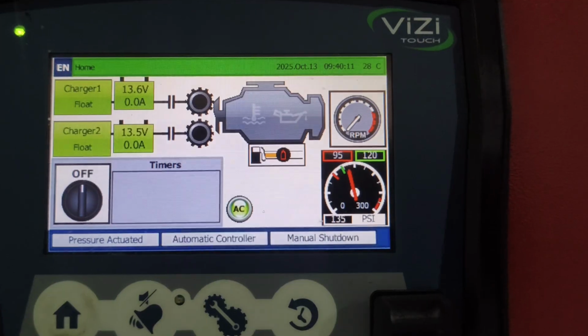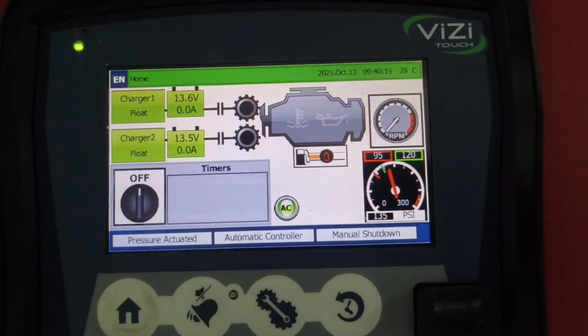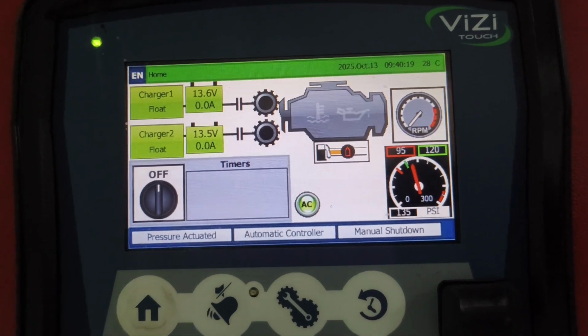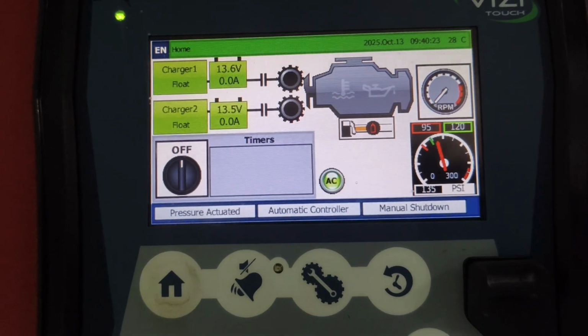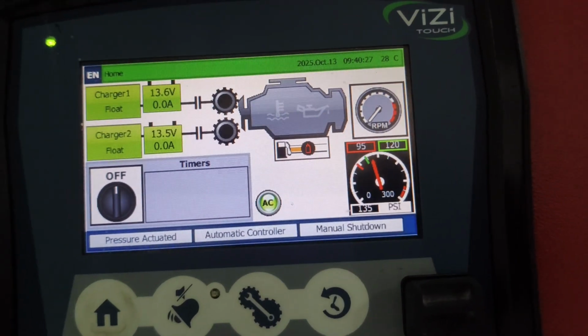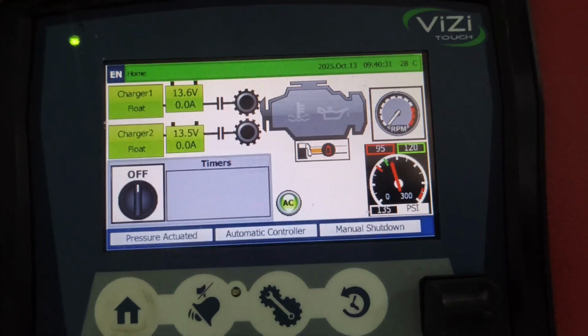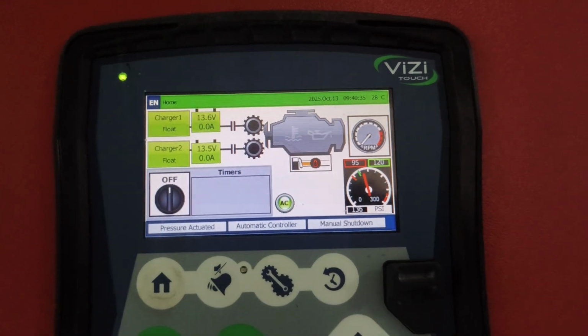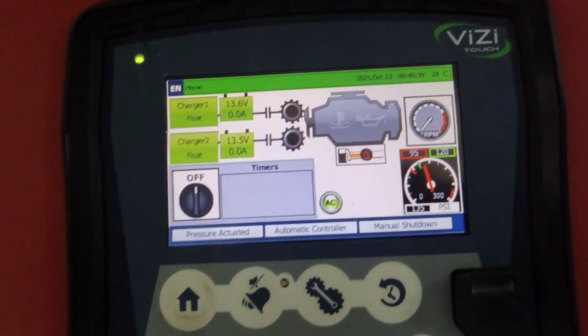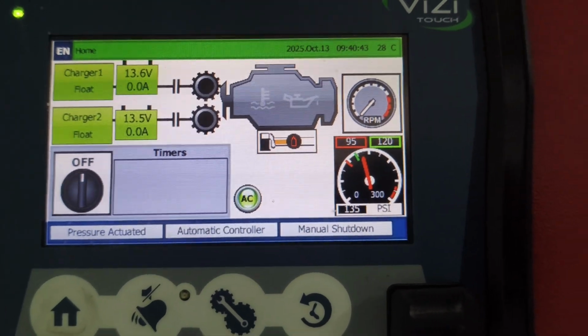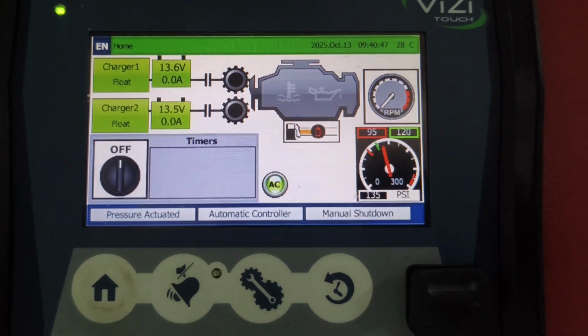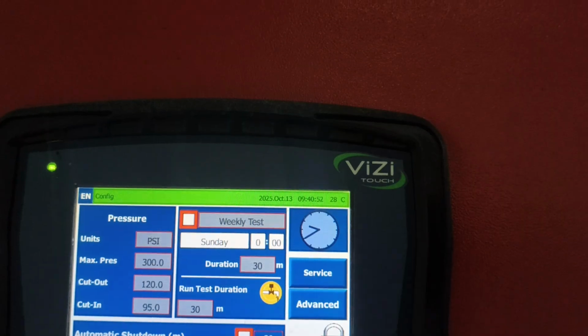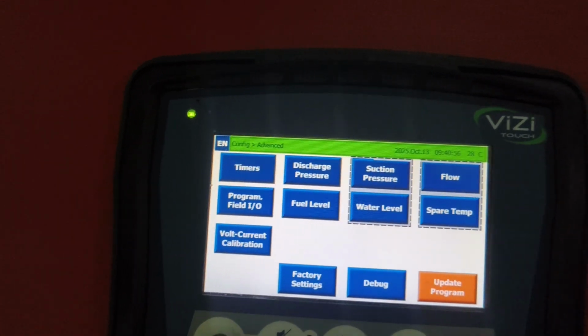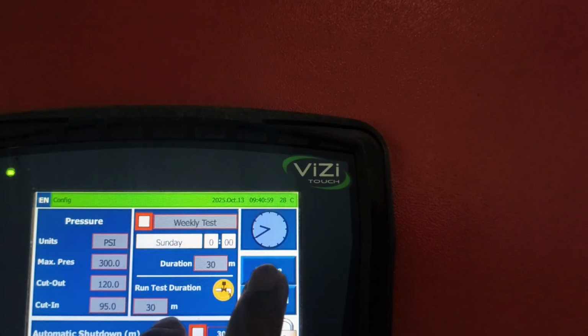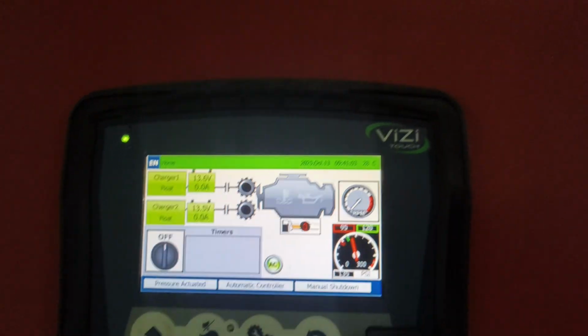So let's confirm from this. You could see from here that the start pressure is 95, the stop is 120, and you can see it's automatic controller, meaning it's going to auto start by itself when the pressure is 95 psi or less. And manual stop means when it runs, you have to come and switch it off by yourself; it will not stop automatically. But by programming, if I make the manual shutdown an automatic shutdown, then it will stop by itself.